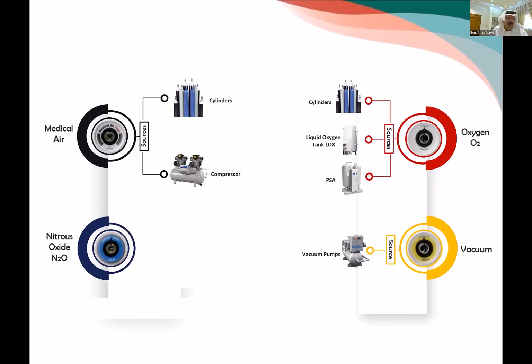You use HTM, or Health Technical Memorandum, or you use NFPA 99. Both of them address the safety of medical gas. Vacuum also: we have vacuum pumps which create suction and send it to the centralized system. And the last one is nitrous oxide, which we usually use for analgesia and for dental, and it's all based on cylinders. We need to see that all of them are working together.